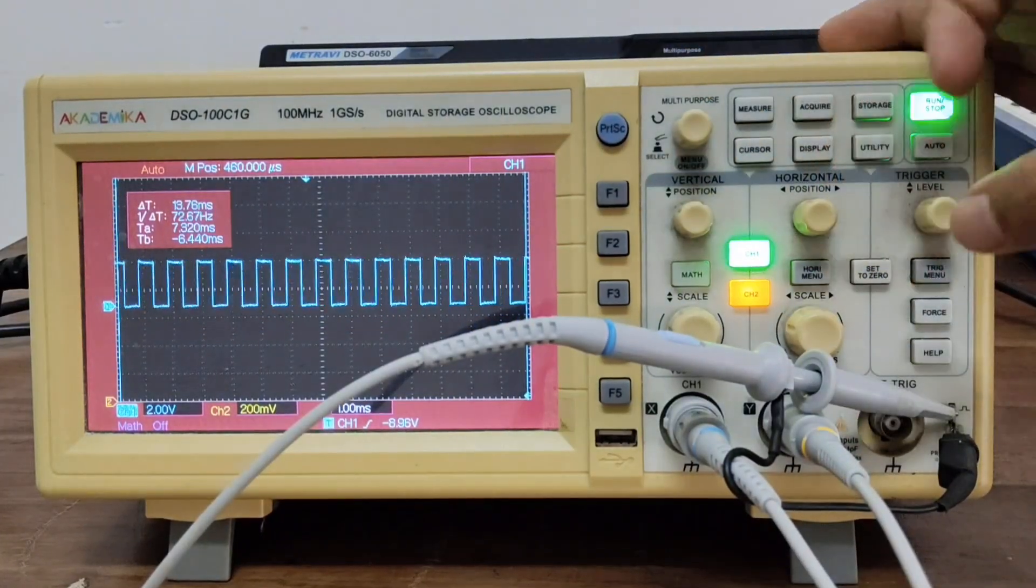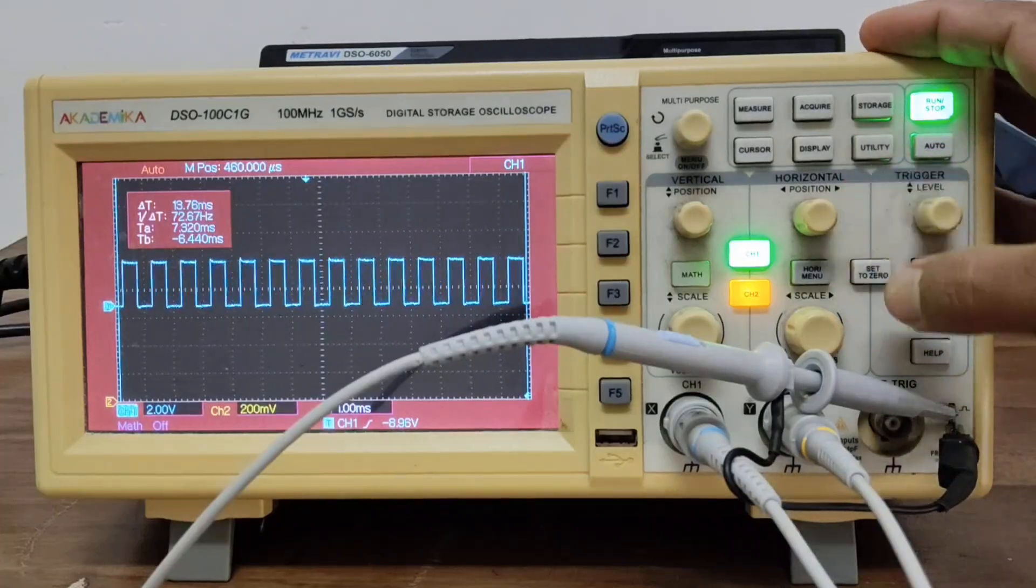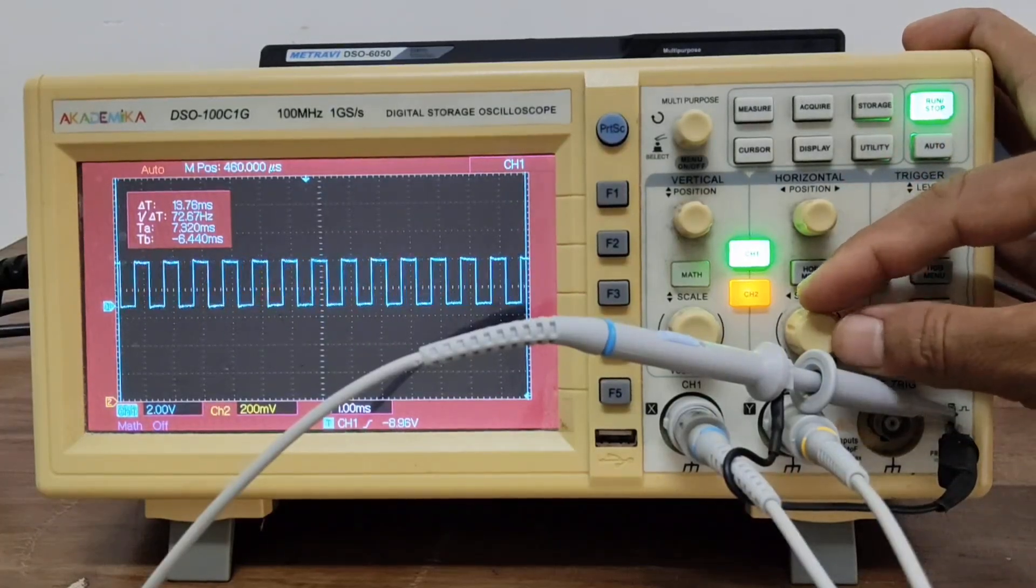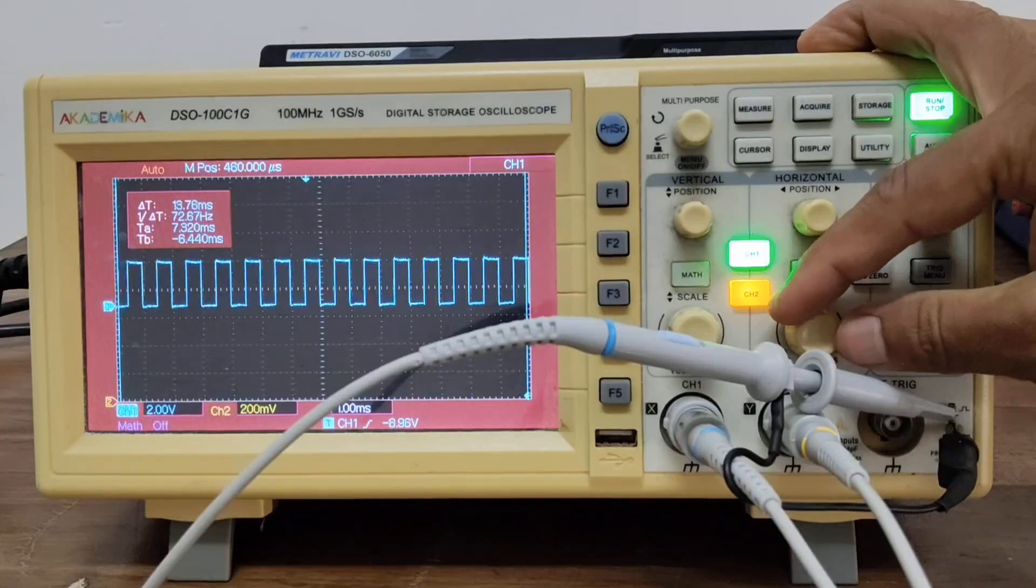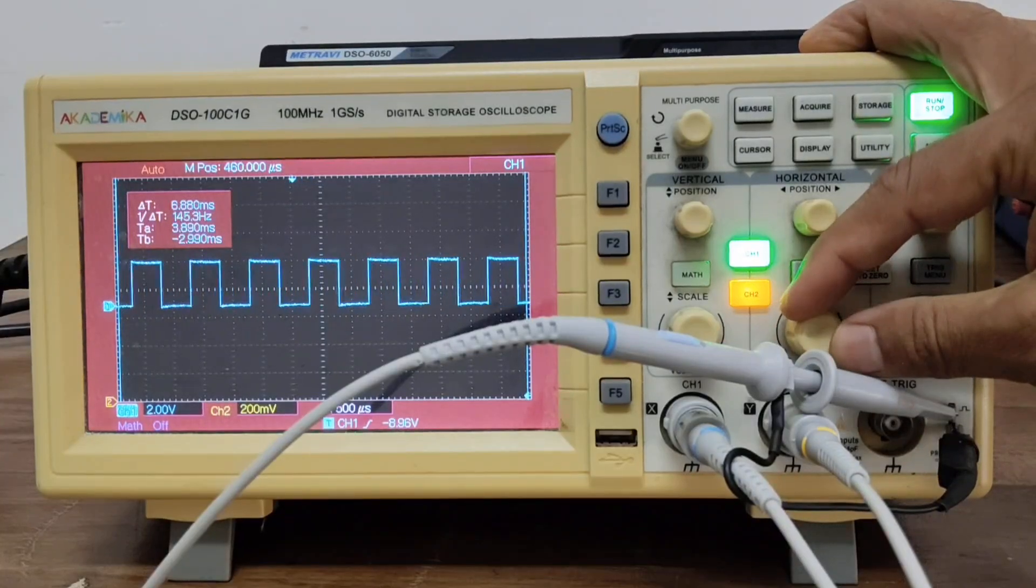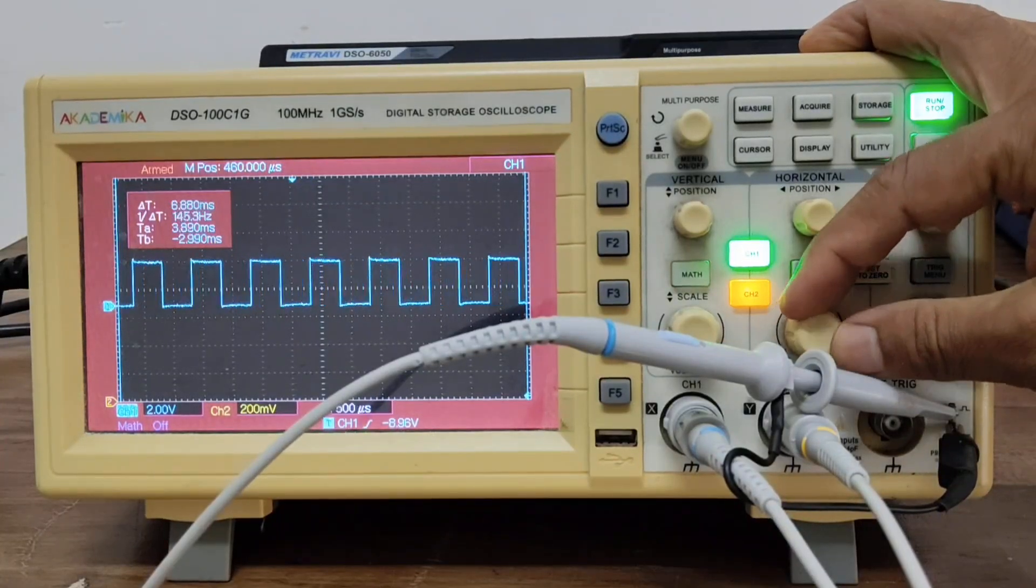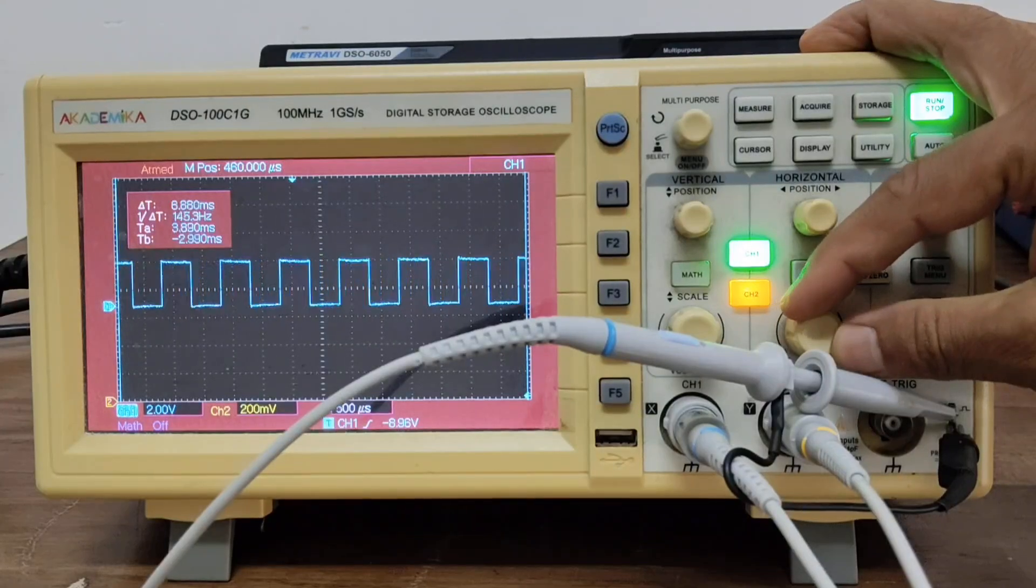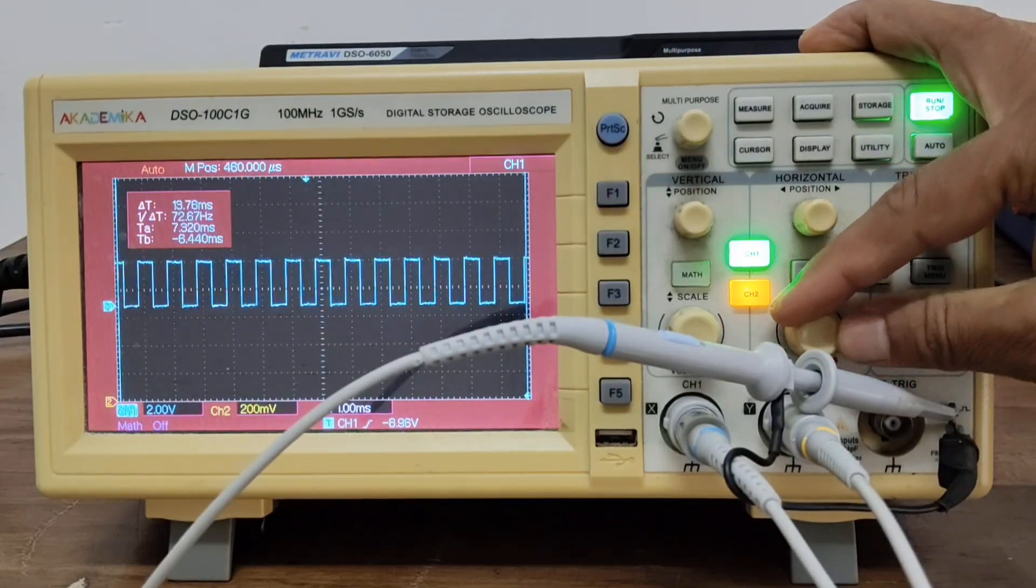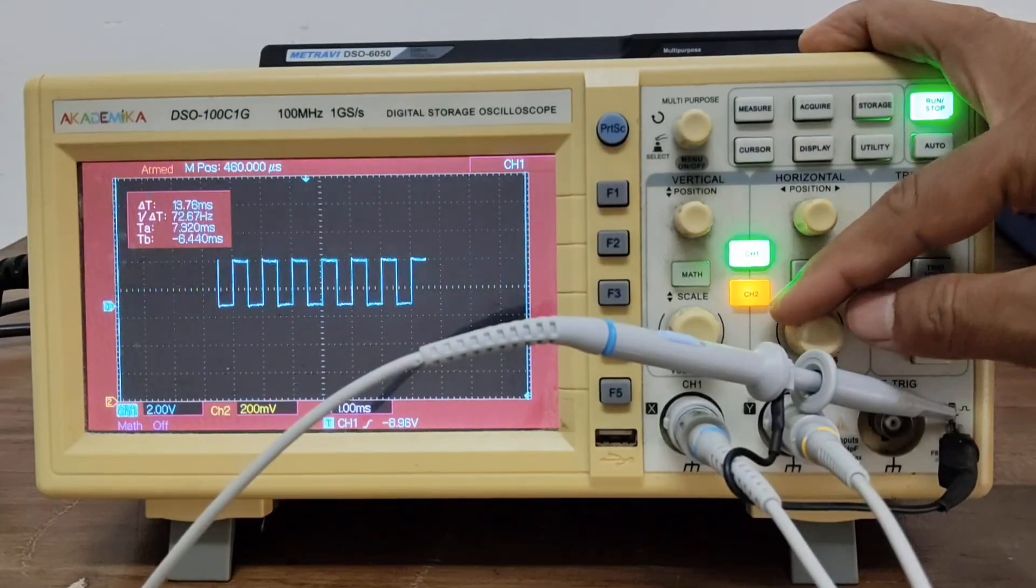And here is the horizontal section. Using the horizontal knob, you can use it to set the time base, how much time each division represents. This spreads out or compresses the waveform in time, you can see.